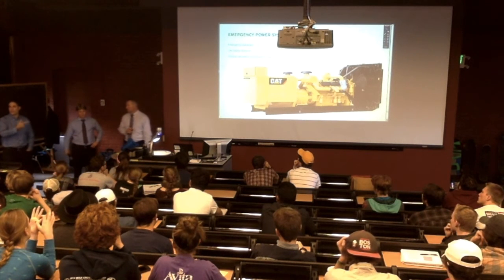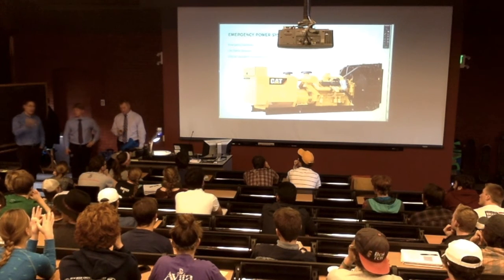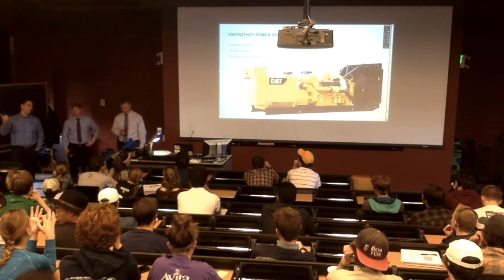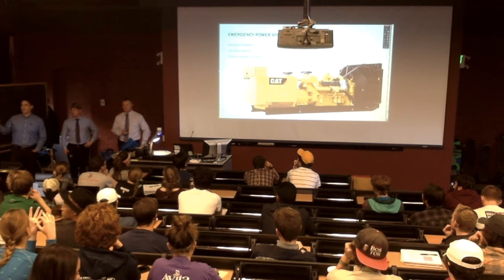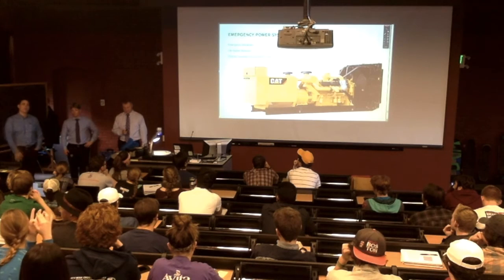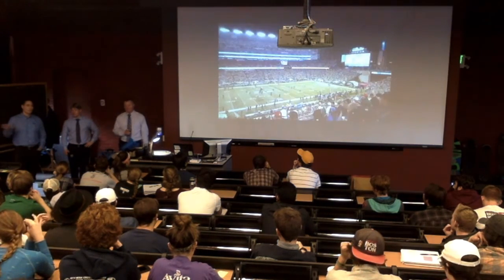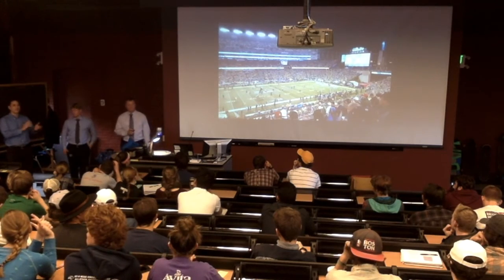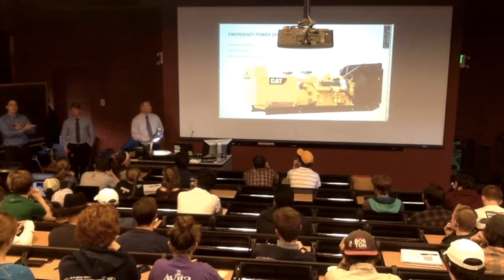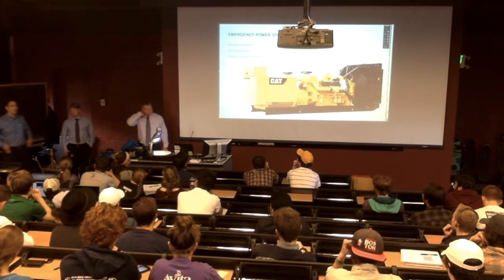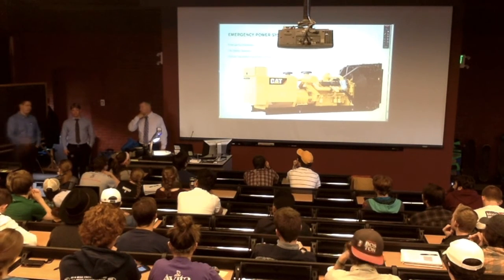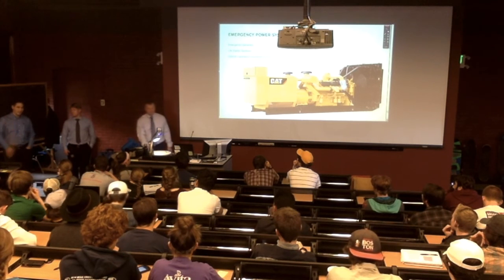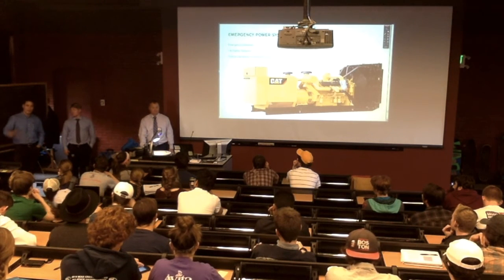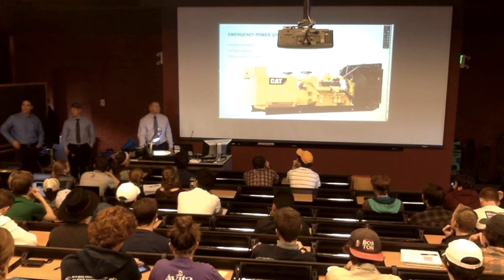On the STEM building, this is a really important part because you've got researchers that are doing experiments that take years to complete, and if they lose power for 10 seconds, they can destroy their experiment. So these guys designed a thing called a transfer switch in a different way, but they'll transfer from a power outage to emergency power very quickly for this process. Whereas if you have a hunting camp or something, it doesn't matter if you're down for half an hour, pull the cord and start the generator.